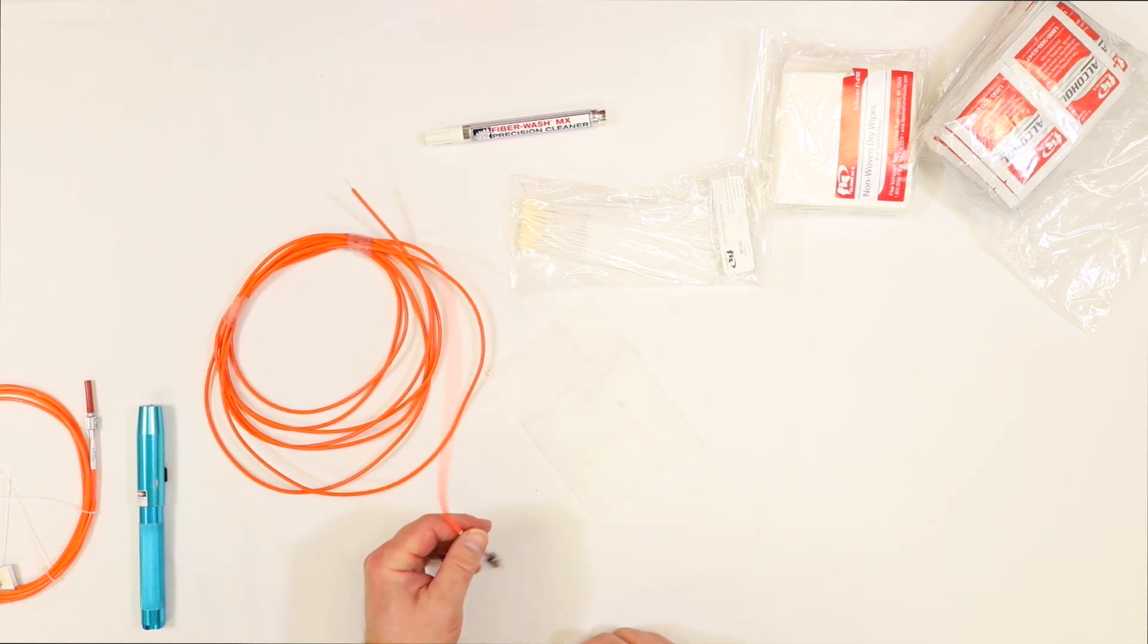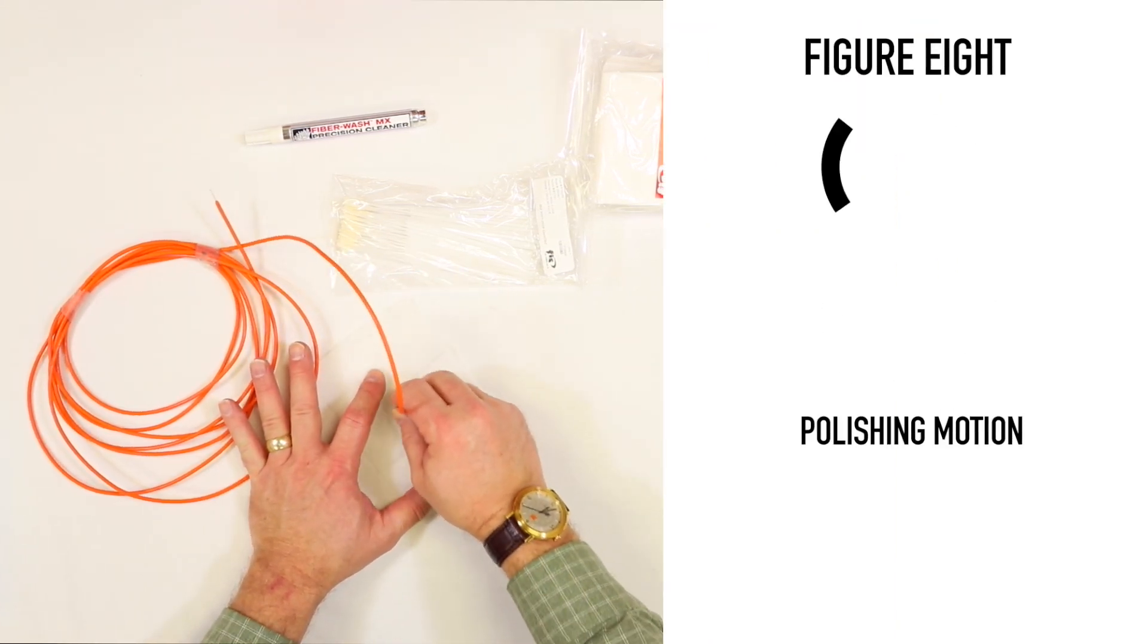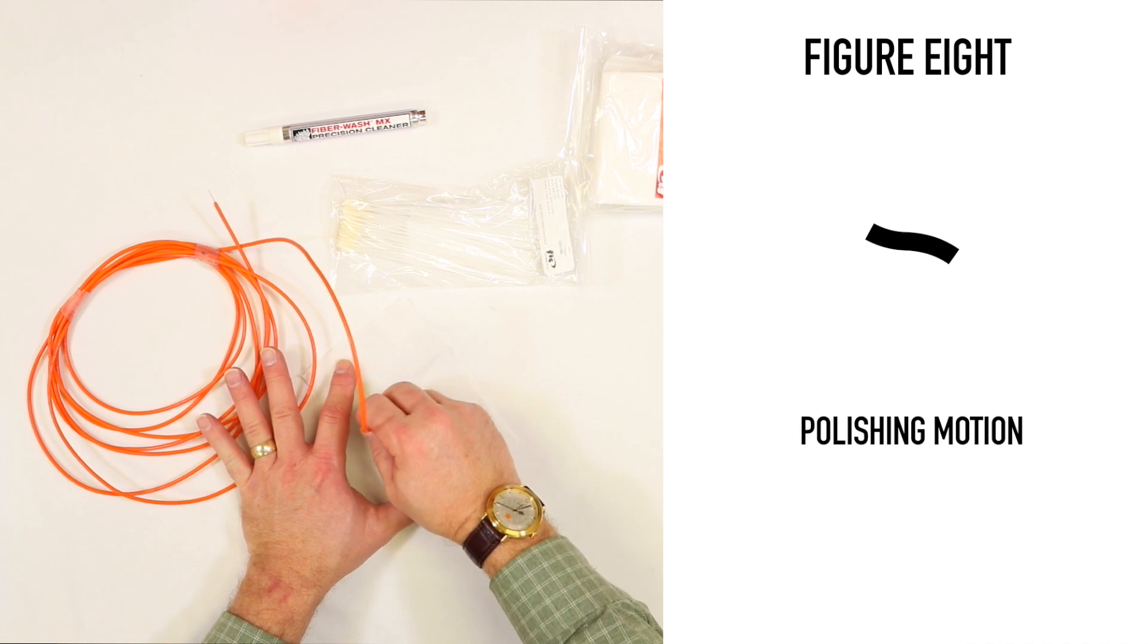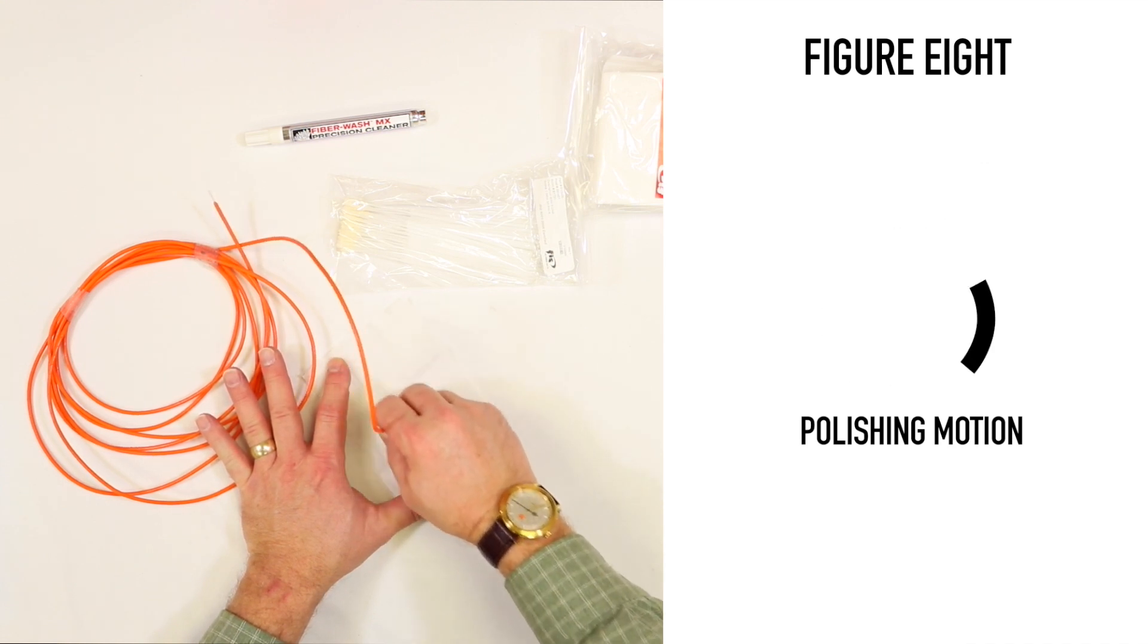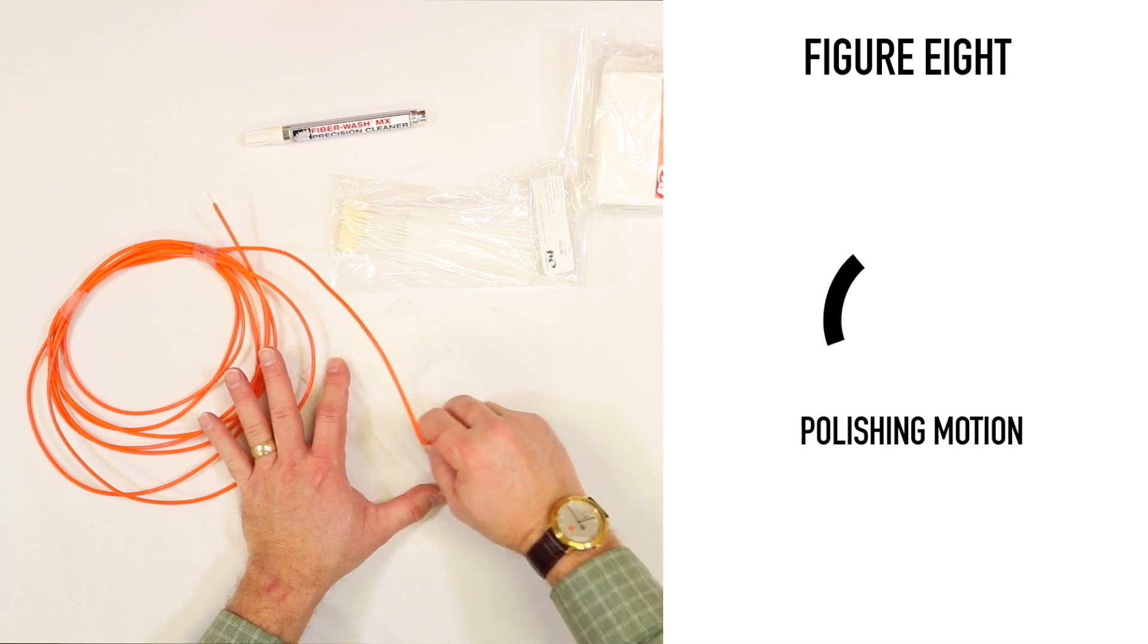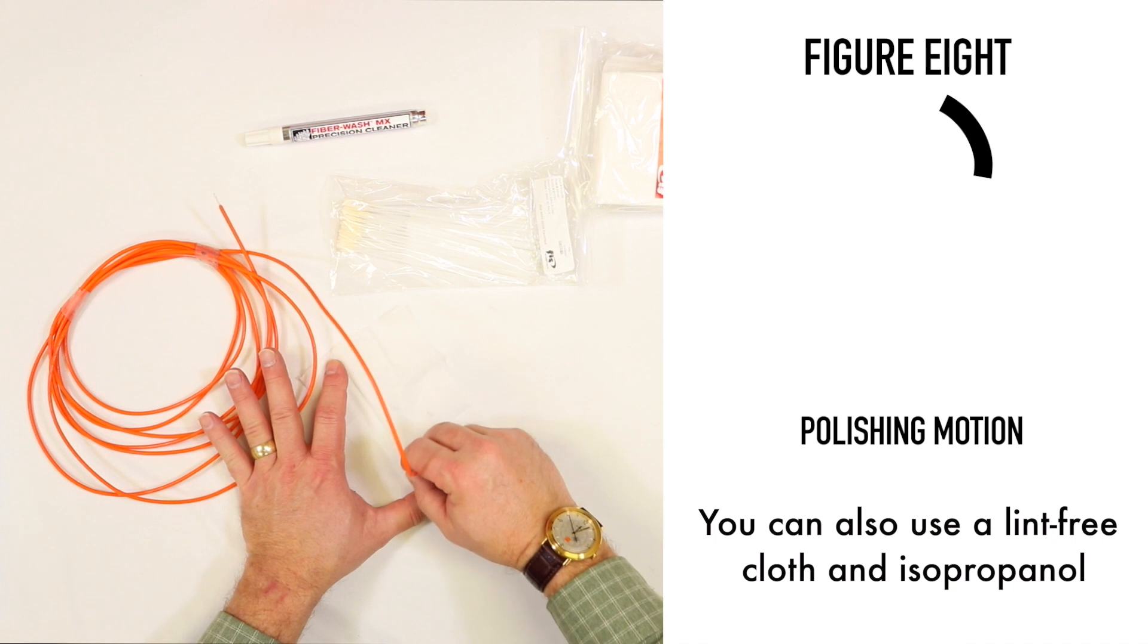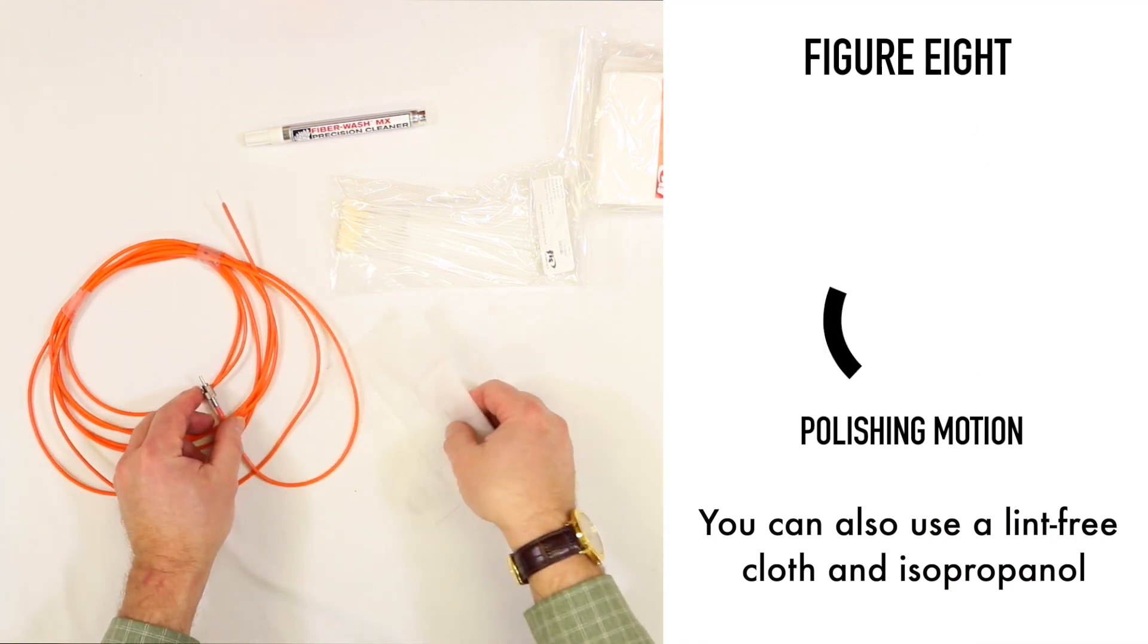Now we'll take the fiber itself and make a figure-eight polishing motion. This is going to clean off the fiber itself and it's not going to leave streaks. You can use this with a lint-free cloth and 100% isopropanol that you can get if you need to in a pinch.